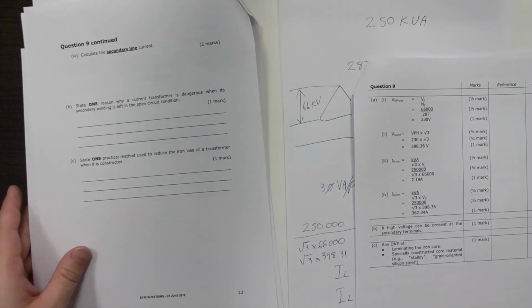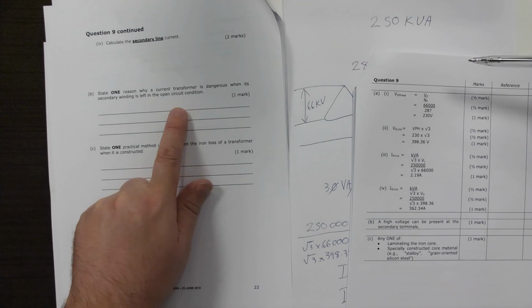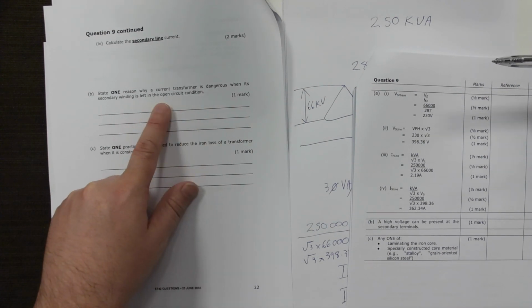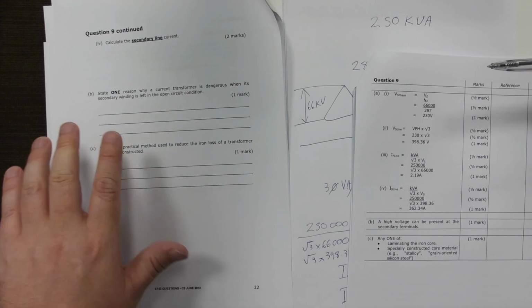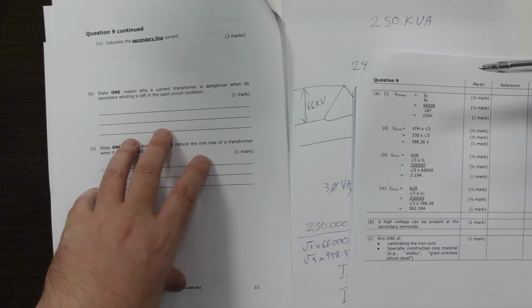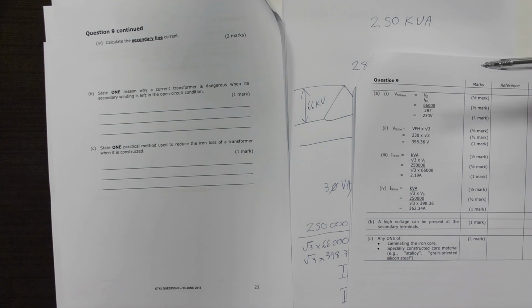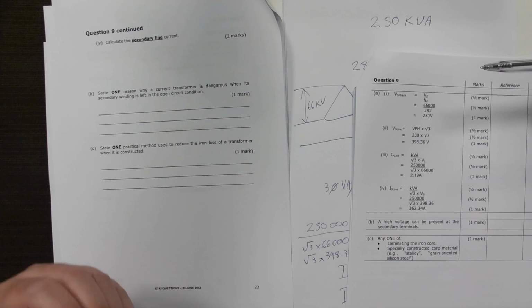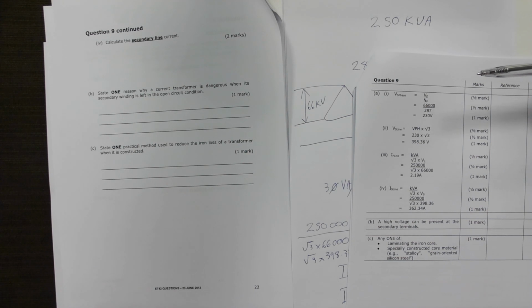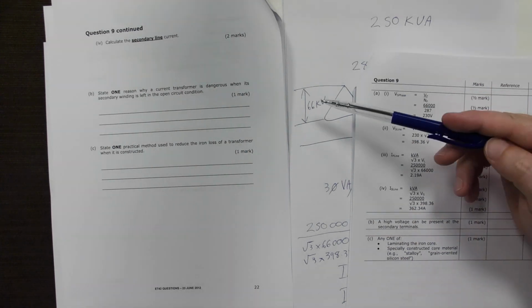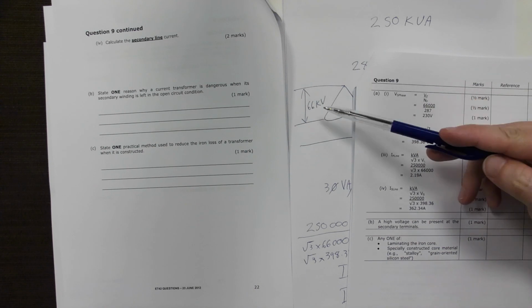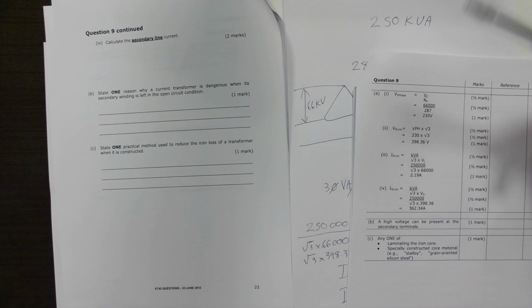Now, our next couple of questions I may as well go through while I'm here. State one reason why a current transformer is dangerous when its secondary winding is left in the open circuit condition. So current transformers are designed to be permanently short-circuited, and then you measure the current flowing through. If you don't short-circuit them, they generate very high voltages across their terminals, and that can damage the current transformer with insulation breakdown, as that voltage is allowed to climb that high, because you actually have a pretty close 1-to-1 ratio type of thing going on sometimes, or it's arguably a step up transformer, so you're stepping up the 66,000 into the high voltage.